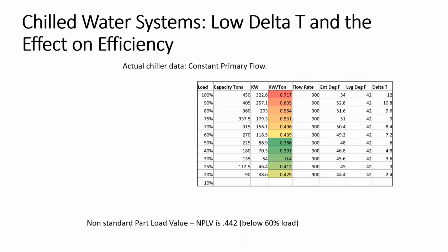That's great, Chris. Yeah, let's do this delta T, the low delta T. So here's low delta T. This is one of those things that, if you notice in this one, the flow rate's constant. So this is constant primary system, but a variable chiller. The chiller is very good as far as getting down to almost 20% of its load, but its highest efficiency ends up here at 50%. That's the kW per ton column. It's a 0.386. That's its most efficient operating point.